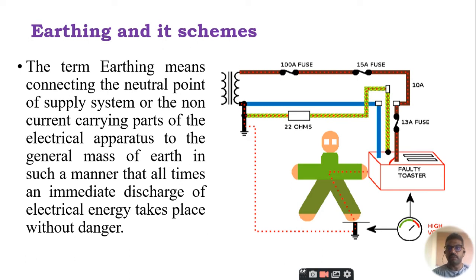There is an immense importance for the earthing. The term earthing means connecting the neutral point of the supply system or the non-current carrying conductor parts of the electrical apparatus to the general mass of the earth in such a manner that at all times an immediate discharge of the electrical energy takes place without any danger. Suppose this faulty part is connected with the earth with a suitable amount of resistance, then this person might not feel the shock, and he or she may not be in a panic condition.